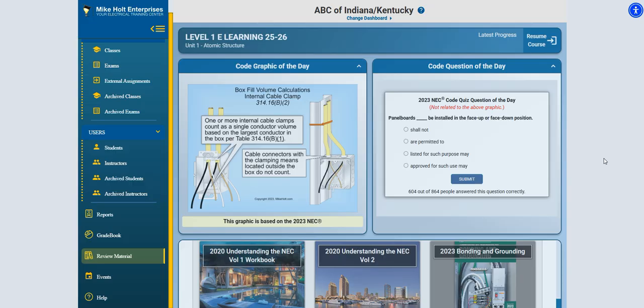If you look at the pictures here, the box on the left is actually what I would call a cut-in box. And those boxes, when they are using non-metallic sheathed cable, will have a clamp inside of them. Most of the time, there's a clamp in the top and the bottom. So that clamp, when calculating the volume for your box fill, would be calculated as one volume. So if I have a number 14 gauge wire in that box, that means if I go to Table 314.16(B), that table says that 2.00 cubic inches would be allotted for a number 14 gauge wire. So when I'm totaling up the cubic inch space needed for that box, I would also include 2 cubic inches for the clamps that are in that box.